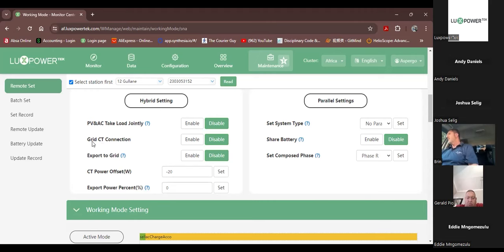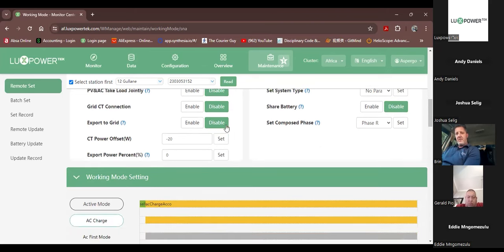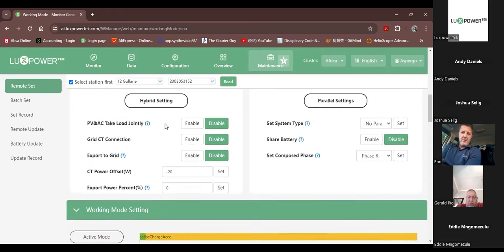Right, grid CT connection: you will only enable this if you have the new 6 kilowatt with the external CT. You cannot enable your old 5 kilowatt with this, it won't work, okay? So this particular connection is for the new machines with the external CT. Export to grid, you guys know how this works. If you are allowed to export to the municipal grid, you can enable this. And then here you just have to put your export power percentage.